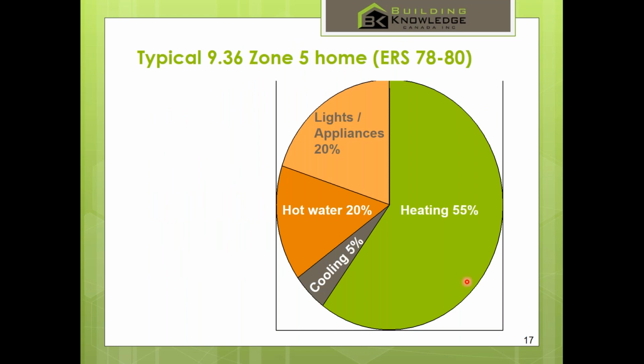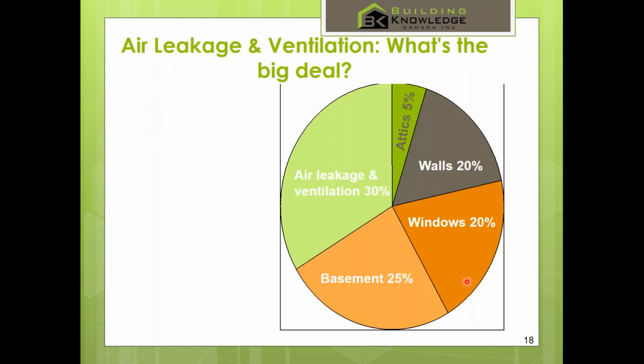So if we look at a typical house in 2012, or the National Building Code today across Canada, this is where the heat is going. 55% is through heating. When we dive down into that 55%, we see that the largest majority of it is actually through air leakage and ventilation, which is why this is a big deal that our load calc should reflect this.